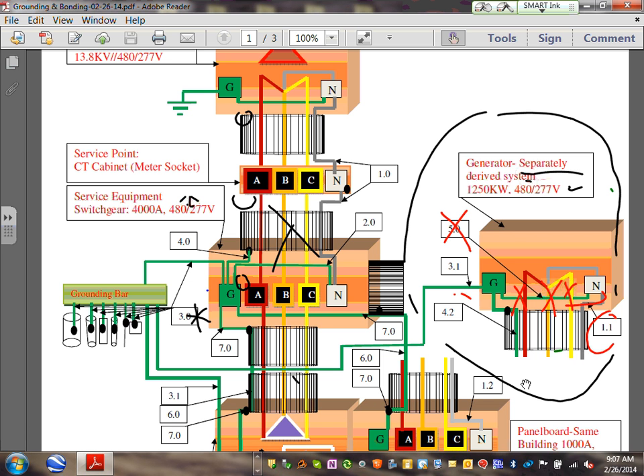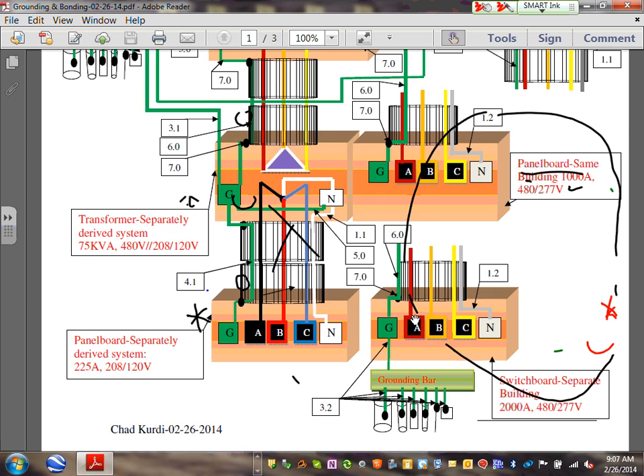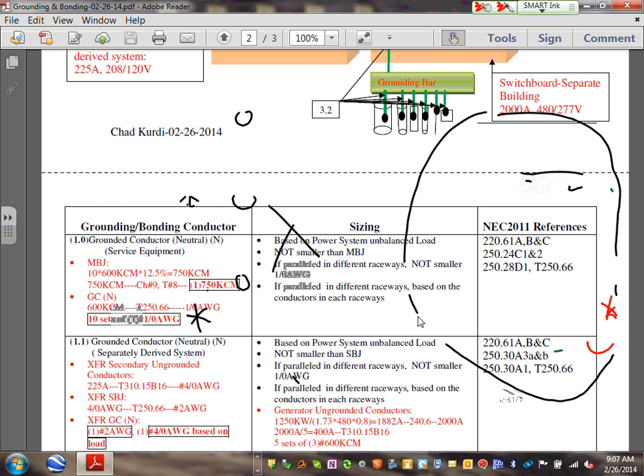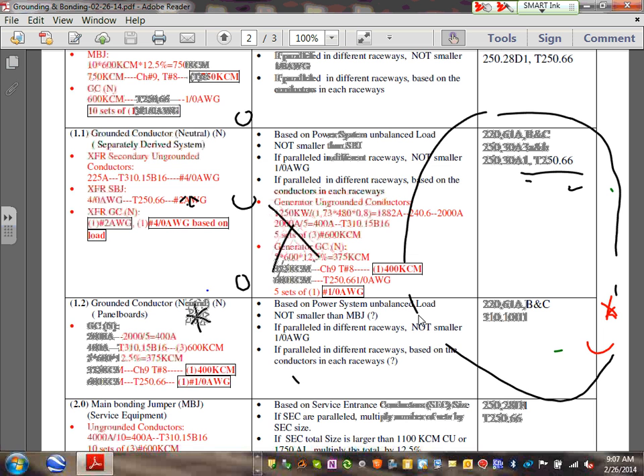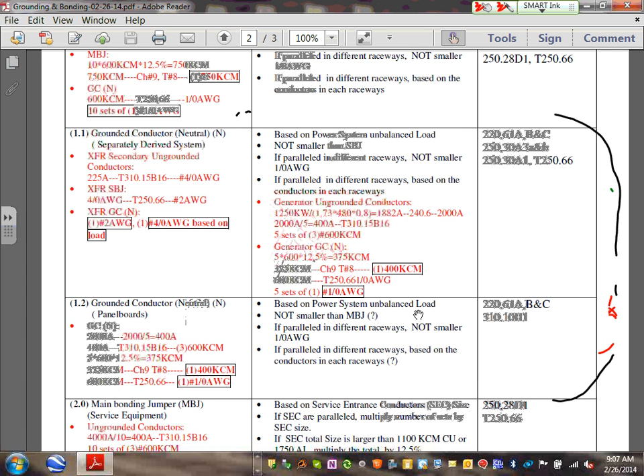Now, okay, we have a separately derived system. We decided to switch the neutral. Then, let's go size 1.1, shall we? So I want you guys to follow up with your friend. I'm going to go number one, size 1.1. Can you see that 1.1 here? That's the neutral for the generator. All right, so the 1.1, gentlemen, the neutral for the generator, is right in here. I'm going to highlight it right in here. Can you guys see that?